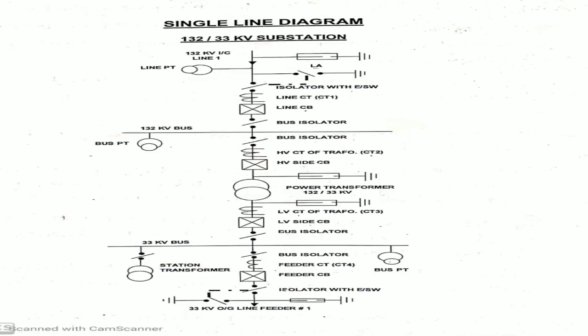Here we can see the single line diagram of 132 by 33 kV. The first one is LA, lightning arrester. Then line PT that is 132 kV line PT, isolator with earth switch, then line CT1, line breaker, bus isolator, bus PT, bus isolator, HV CT for transformer that is CT2, HV side circuit breaker.